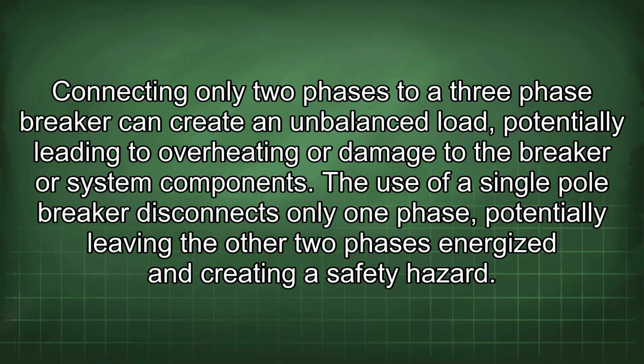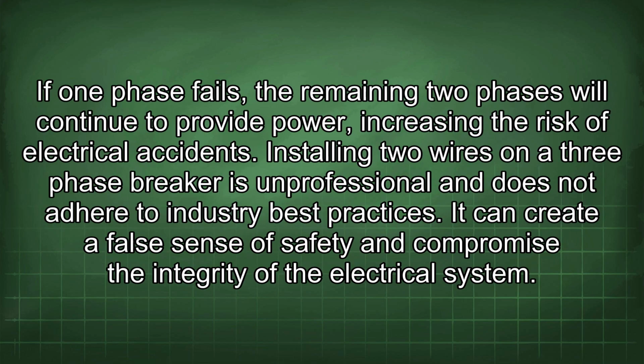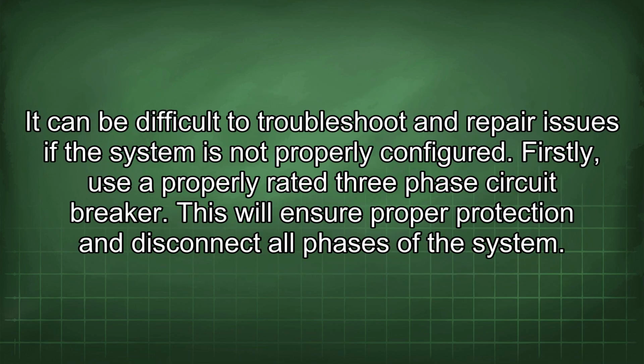The use of a single-pole breaker disconnects only one phase, potentially leaving the other two phases energized and creating a safety hazard. If one phase fails, the remaining two phases will continue to provide power, increasing the risk of electrical accidents. Installing two wires on a three-phase breaker is unprofessional and does not adhere to industry best practices. It can create a false sense of safety and compromise the integrity of the electrical system. It can be difficult to troubleshoot and repair issues if the system is not properly configured.